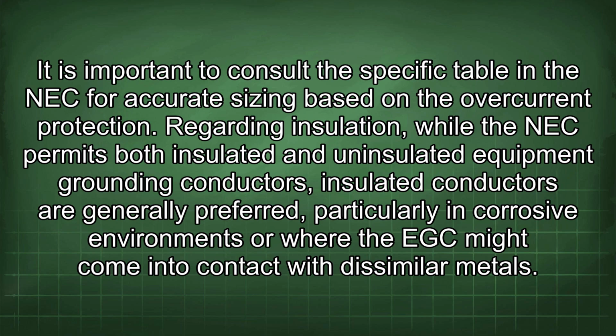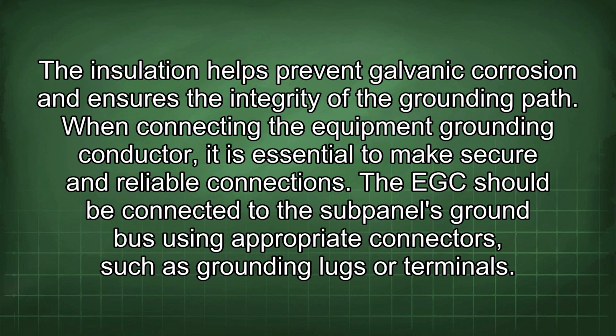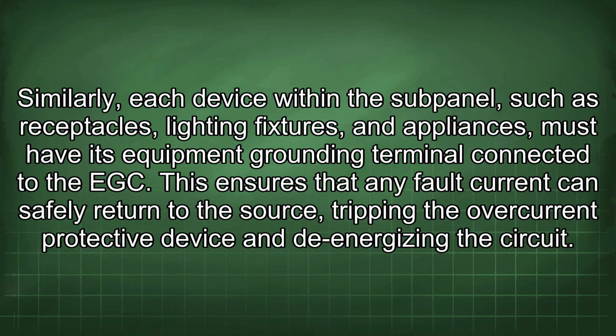Regarding insulation, while the NEC permits both insulated and uninsulated equipment grounding conductors, insulated conductors are generally preferred, particularly in corrosive environments or where the EGC might come into contact with dissimilar metals. The insulation helps prevent galvanic corrosion and ensures the integrity of the grounding path. When connecting the equipment grounding conductor, it is essential to make secure and reliable connections. The EGC should be connected to the subpanel's ground bus using appropriate connectors, such as grounding lugs or terminals. Similarly, each device within the subpanel, such as receptacles, lighting fixtures, and appliances, must have its equipment grounding terminal connected to the EGC.